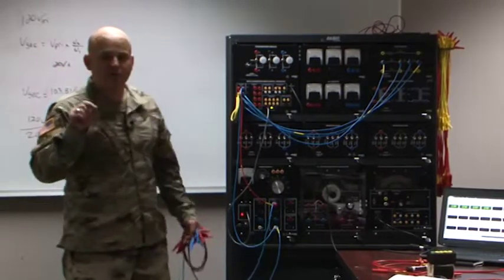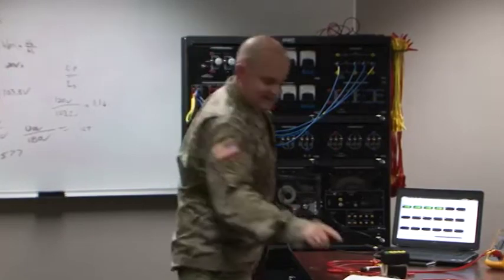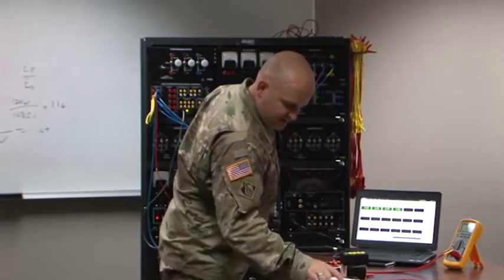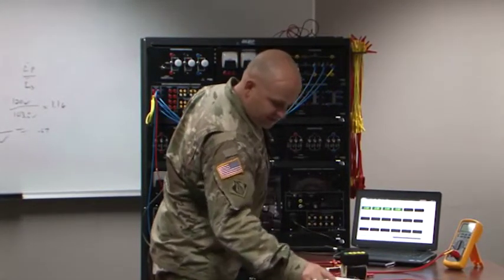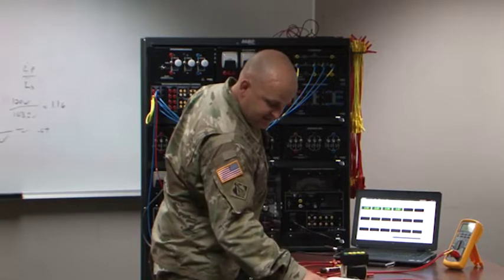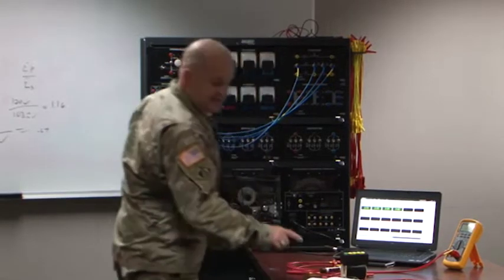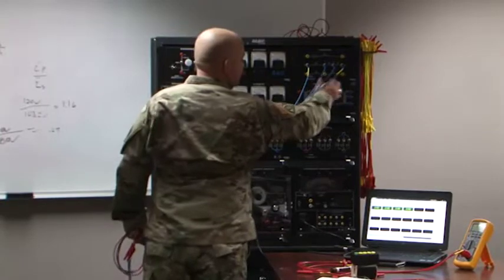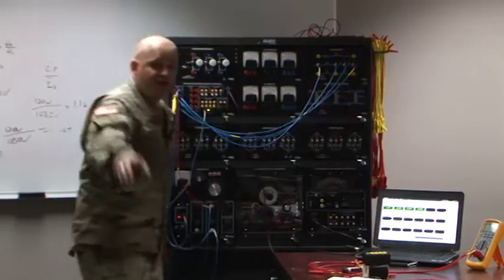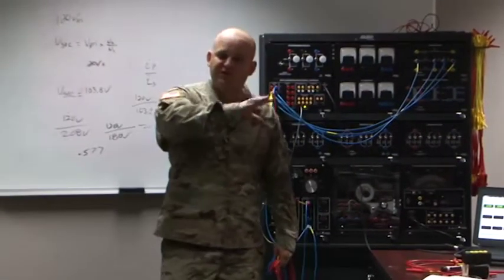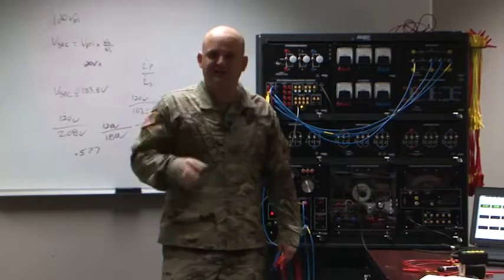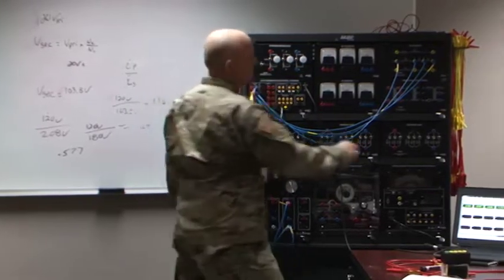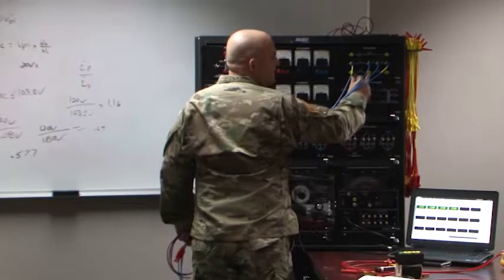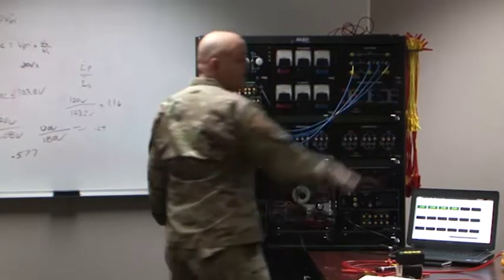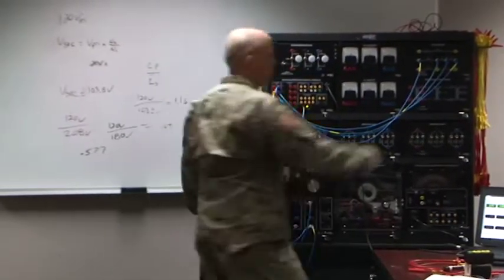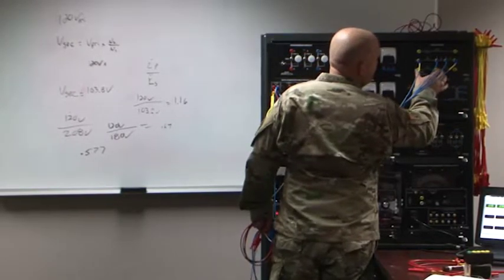Pay attention to what voltages you're actually putting in, because let's look over here on step 13. It's going to tell you that you're going to be tapping into 9 and 6 on this one right here, and you're going to read the chart, and it's going to say using 120, this is your setting. So you're going to immediately think I apply 120. Well, based on what I just told you, if I applied 120 to right here and tapped off right here, you're going to get 208, or actually that one right there would be even more - that'd be by a factor of 2.